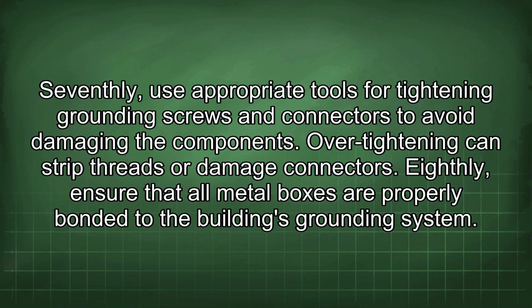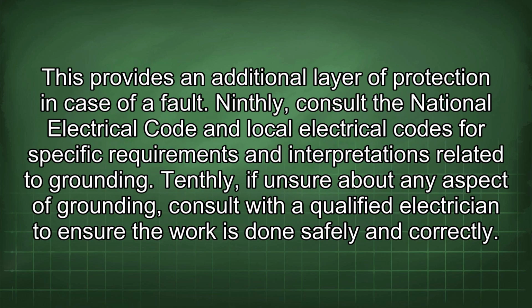Seventhly, use appropriate tools for tightening grounding screws and connectors to avoid damaging the components. Over-tightening can strip threads or damage connectors. Eighthly, ensure that all metal boxes are properly bonded to the building's grounding system. This provides an additional layer of protection in case of a fault. Ninthly, consult the National Electrical Code and local electrical codes for specific requirements and interpretations related to grounding.